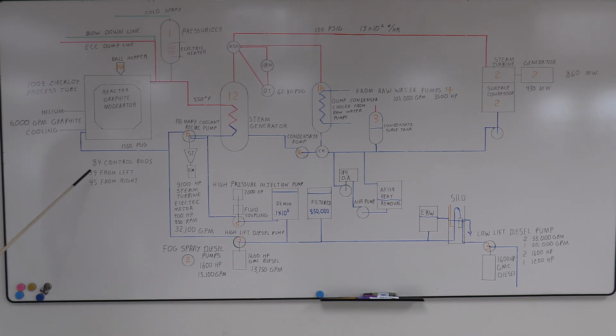To control the reactor, there are 84 control rods, 39 from the left and 45 from the right. They're designed to go in 75% in 1.5 seconds. He had safety rods and he had control rods. But this is what controlled the reactor. Used high pressure oil, hydraulic system to fire them in.